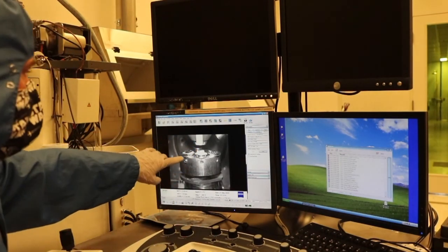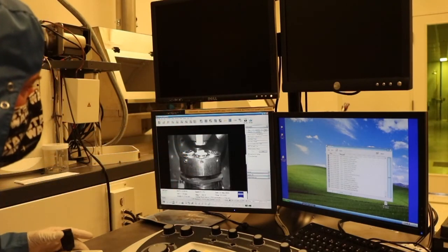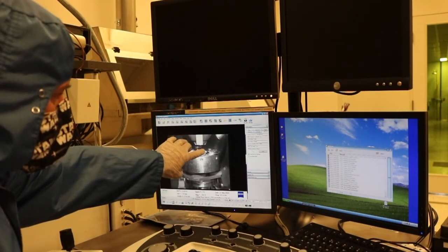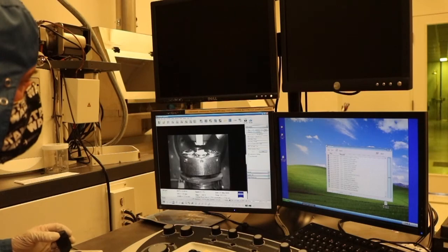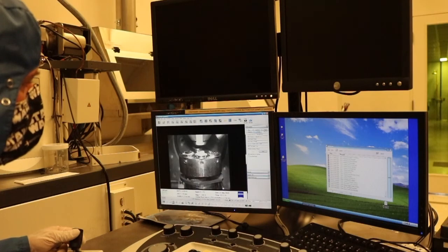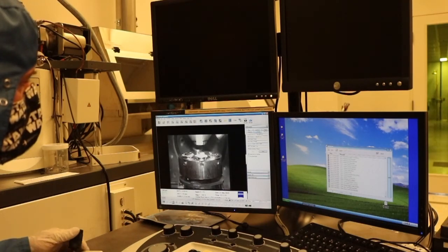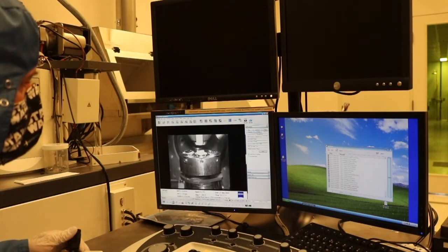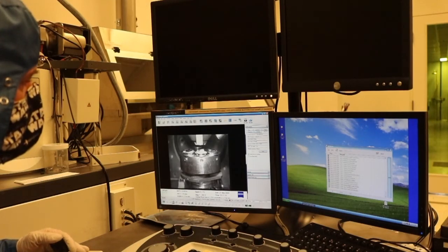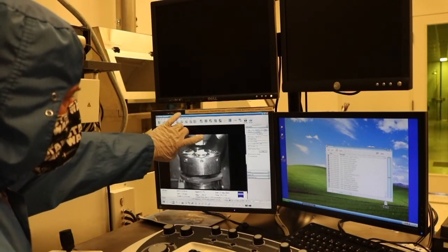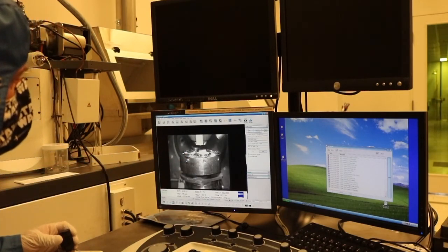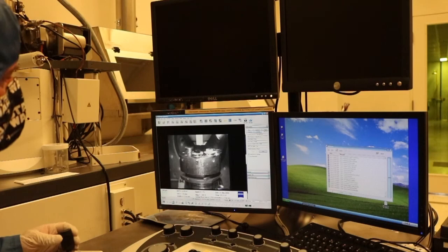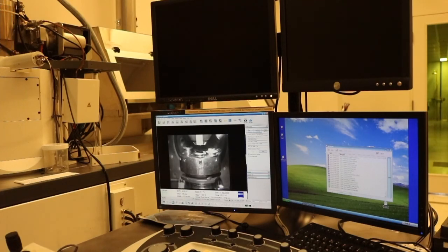A few other visual cues to look for is the brightness here, as well as whether or not there's a shadow. You can see that it got dark across the front there. And then also whether or not the front edge of the sample holder is in focus. Okay. And that's right about there. So a small amount of shadow, focus, and then the height. We're actually going to start off with the sample just to the left here. So I'm actually just going to rotate that sample into position. And that's where we'll start our initial imaging.